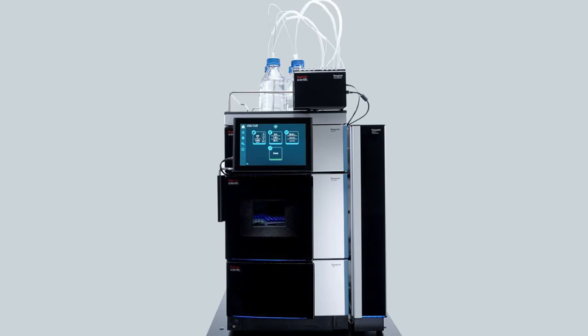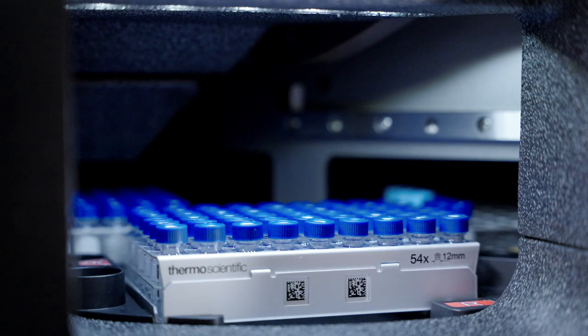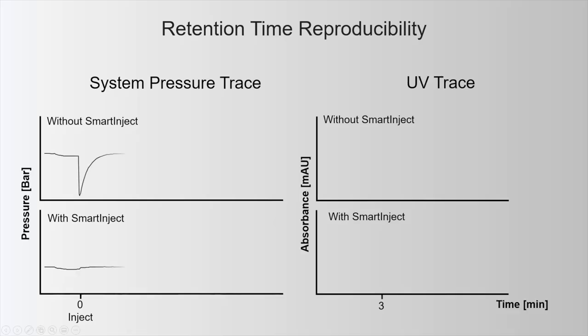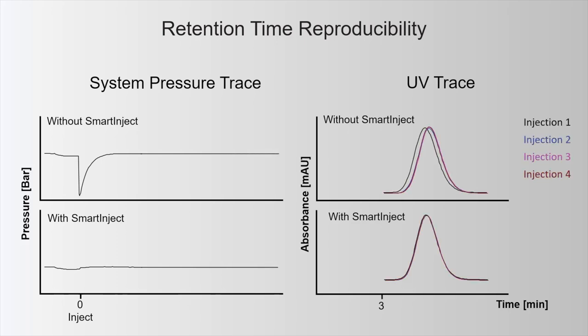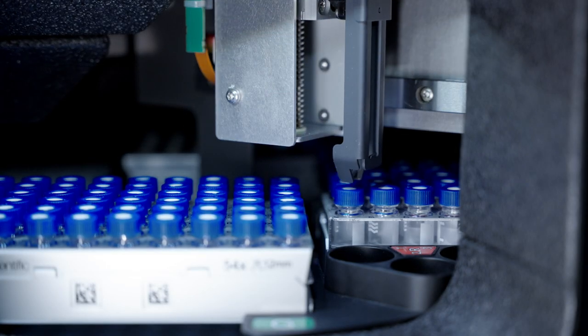The cutting-edge Thermo Scientific Vanquish split-loop autosampler redefines sample introduction with low dispersion fluidics and a unique metering device for high injection volume linearity and precision. Smart Inject technology automatically reduces the pressure drop during injection, enhances retention time precision, and extends column lifetime.